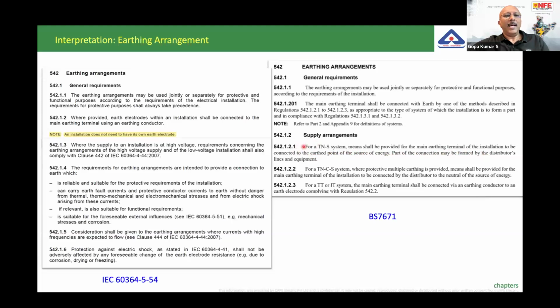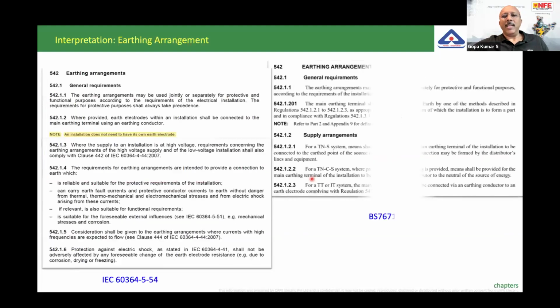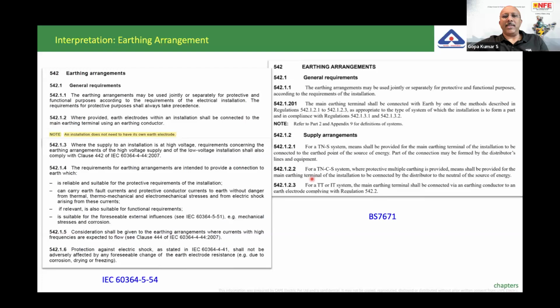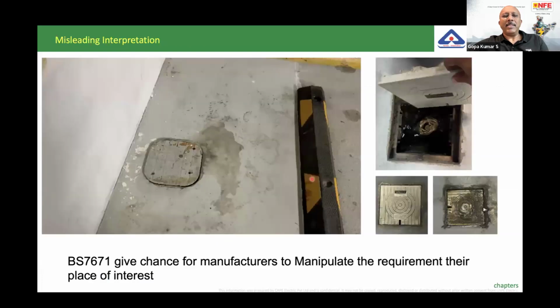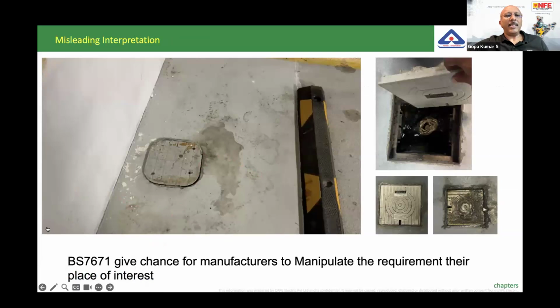So basically, they change the content a little bit in such a way that it suits their requirement. It suits because people have had the habit of reading these wordings for several decades. So they made it in this fashion. Similarly, TN-C-S, TT. Now, you see there is a difference between what is written in IEC and what is written in BS 7671. Now the definition of earth electrode given in BS 7671 is first the vertical rod, then the plate, and so on. So as a result, what happens is people always have the habit of reading the first thing, and the balance we don't read. As a result, misleading or misinterpretation goes to the market.